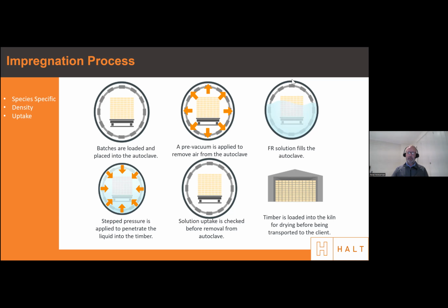This comes back to how the timber was actually tested. If a timber passed testing with 38 kilos of dry fire retardant per cubic meter, the process needs to guarantee the timber is impregnated with a minimum of 38 kilos per cubic meter. So the software, the process, ties in very closely to how the timber was tested and classified. It's part of the manufacturing process that we must demonstrate and ensure consistent performance going forward with every timber species.